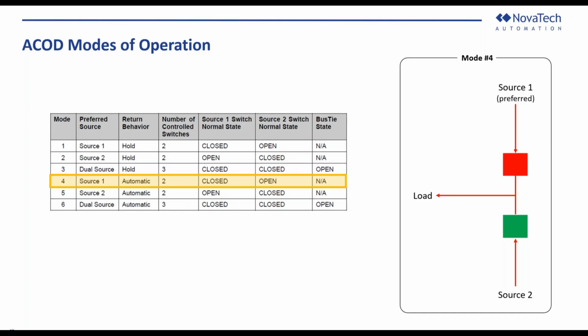Going down to the other two modes, modes 4 and 5, things do get a little bit more interesting here. Mode 4 is similar to mode 1 in that source 1 is the preferred. So switch 1 starts out closed, switch 2 starts out open. If potential is lost on source 1, ACOD will go through the same steps to transfer off of source 1 to source 2, closing in on source 2. And now ACOD is monitoring and waiting for that potential to return on source 1, because it does want to switch back. So once it sees that the potential has returned and all the criteria have been met, it will return by opening source 2, closing back on source 1, and being back in its normal operating mode.